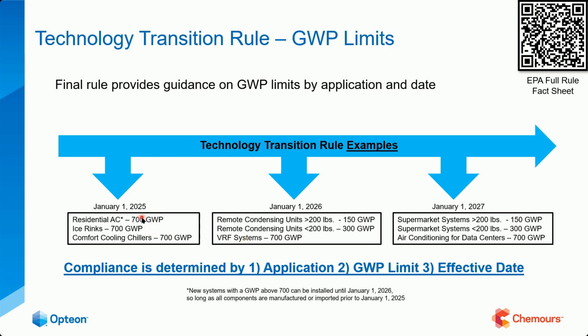Okay. So when we look at 700, basically what this is telling us over here at the residential AC, by the way, is that we can't produce any R410A equipment anymore after the first of this year. We can't produce it. We do have a sell-through date until 2026, but we can't manufacture it because this 700 GWP is the max, and 410A is right around 2088, somewhere thereabouts. So the 2 big players right now are R454B and R32. Now over here at the end, it's pretty much identical to the remote condensing units. However, we're talking about supermarket systems. They took this in steps because they didn't want to do it all at one time and cause a lot of confusion. So the easiest place to start was your residential, light commercial stuff.